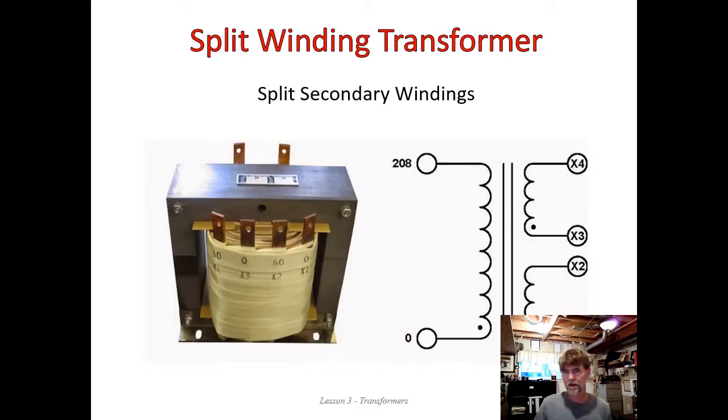Okay, last thing we're going to look at, there's a number of slides here that talk about split windings and taps. We've talked a little bit about multi-taps, but it's really fairly typical for this arrangement that we're looking at right here, called a split secondary. Very often you'll get a split primary as well, where there are actually two coils, two secondary coils in this case. And oftentimes there might be two primary coils as well. So there would in fact be 4 coils rather than just 2. Rather than just a primary and a secondary coil, there would be 2 of each.